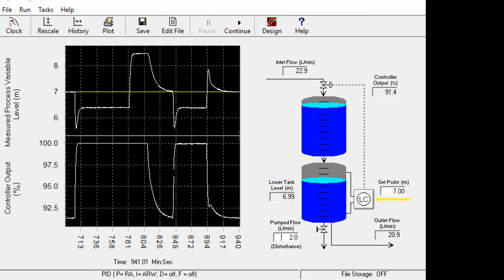Comparing these two scenarios: in the first case, without anti-reset windup, the controller wound up and it took a really long time for the controller to take any action. But with anti-reset windup, the integral action was turned off when the valve saturated, so the controller can take action as soon as there is a change in the opposite direction.